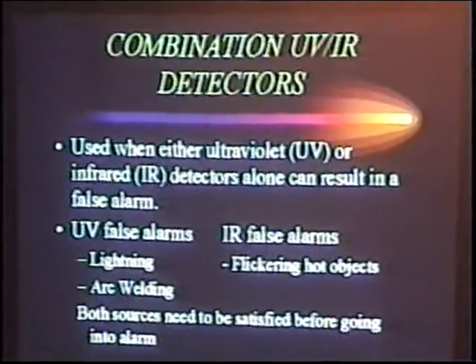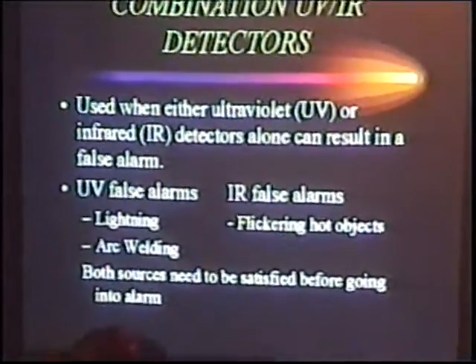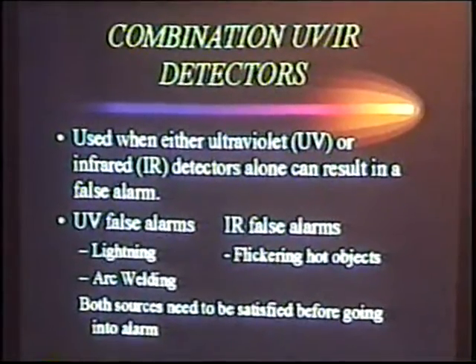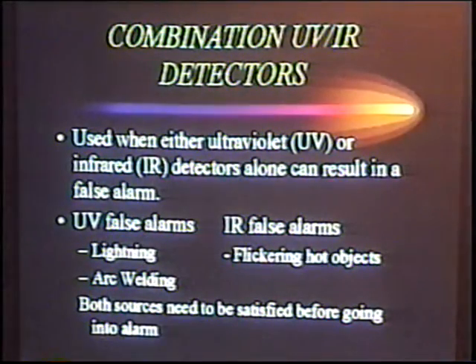We use combination UV/IR detectors as well. When do we use them? They're typically used when either UV or IR on its own can result in a false alarm. Once again, kind of like a cross zone situation, we want to satisfy the same detector with both a UV and IR source. Common false alarms for UV are lightning and arc welding. They go into alarm every single time. Common IR false alarms are what we talked about, black body radiation. So we need to be careful as to when we want to use the detection and where we want to aim it.